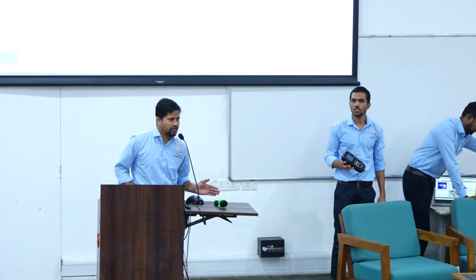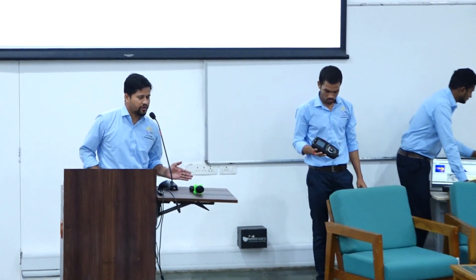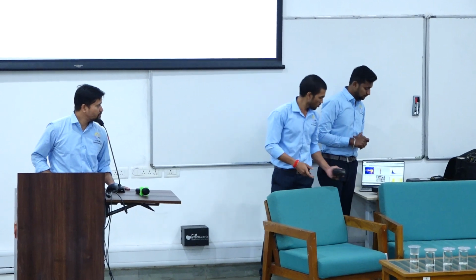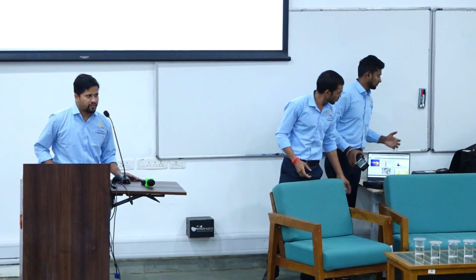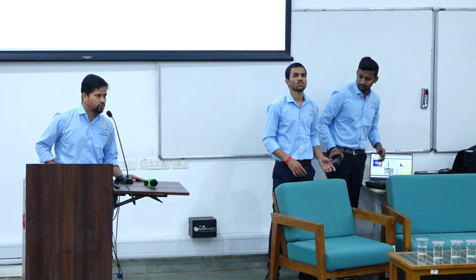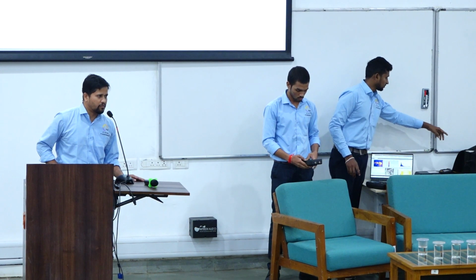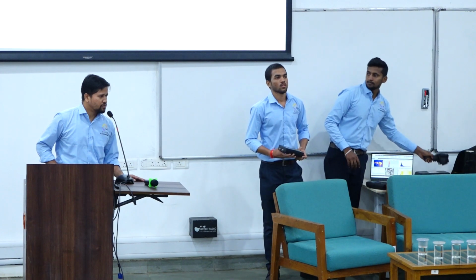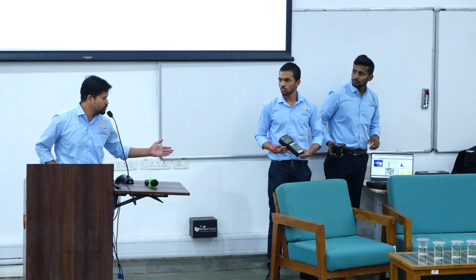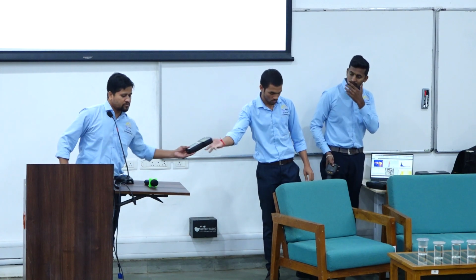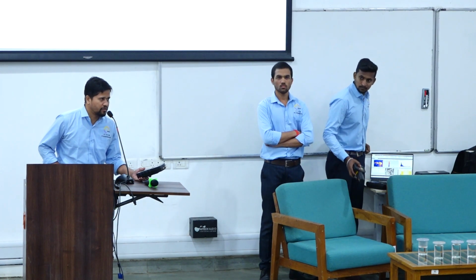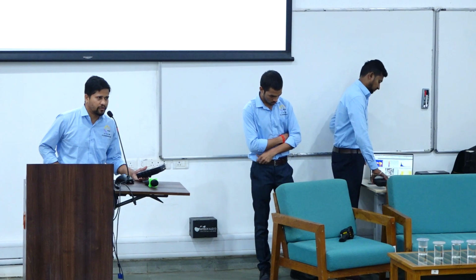Our another very dedicated instrument is the flue gas analyzer. With the help of this instrument, on the boiler side, when we need to measure nitrogen oxide or sulfur oxide, we can measure these parameters. When we are going for pumping efficiency, we need to measure power as well as water flow. For measuring water flow, we can use this flow meter, with which we can measure water flow in any pipe.